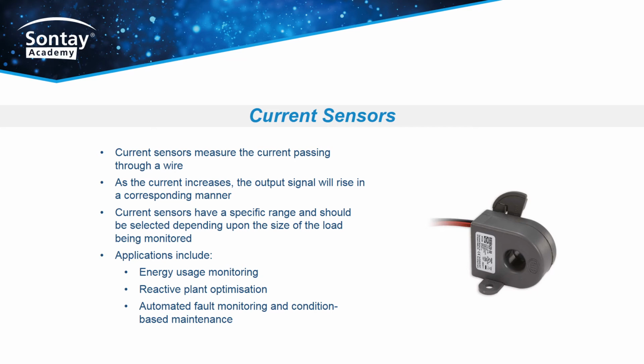Rudimentary power calculations can be performed using a current sensor by assuming that the supply voltage is constant. Condition-based monitoring allows alarms to be generated when current demand exceeds a given threshold. For example, variance in fan power that would be seen from a broken damper or other blockage.